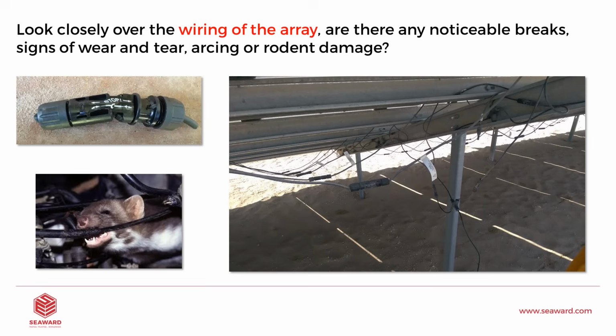And then also you can see in the top left-hand corner, we have an image of an MC4. Now this hasn't been crimped correctly inside, so the little metal plating inside hasn't been done correctly. And this can again cause an arc fault inside, which is causing the connection to melt. On a very serious level, this could be a fire hazard. On a less serious level, this is really going to drop out production of the entire plant. So this is why it's very important to have the correct test equipment.